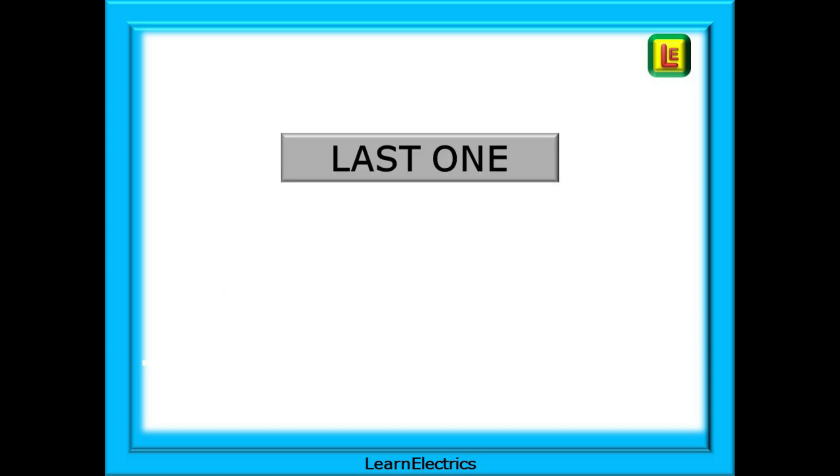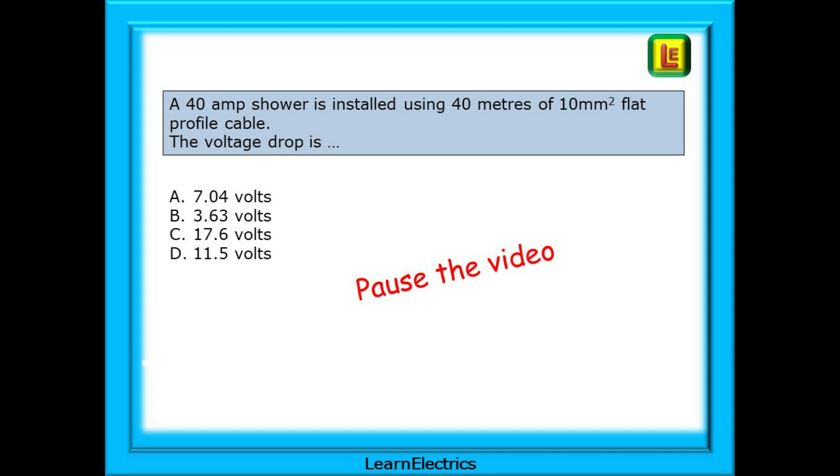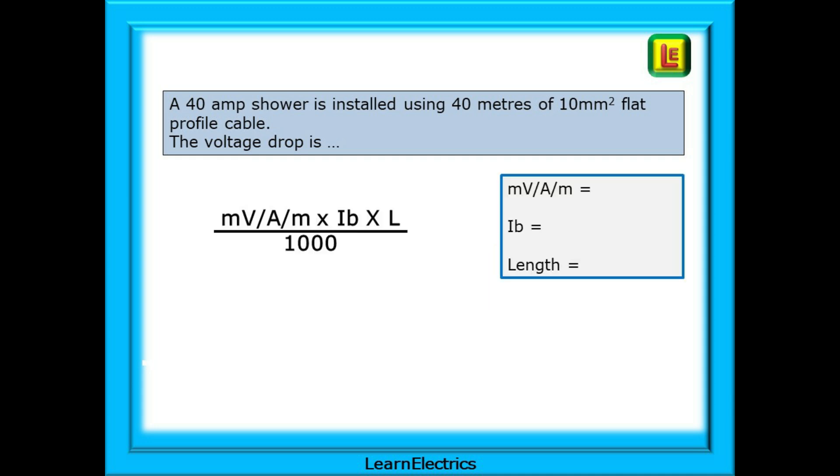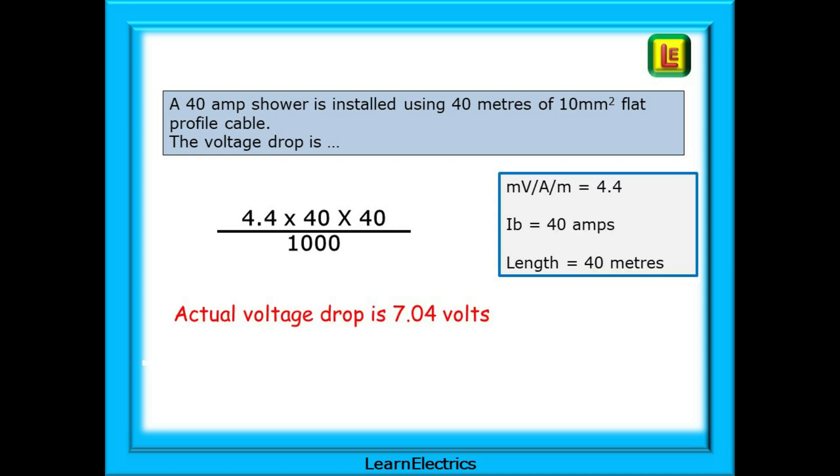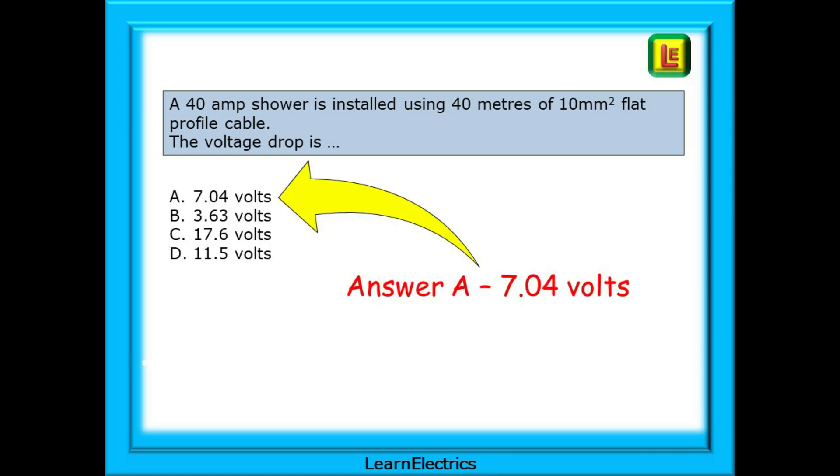And the last question for this video. A 40 amp shower is installed using 40 metres of 10 square millimetre flat profile cable. The voltage drop is 4 potential answers. Choose the correct one. Again pause the video and work through the question yourself. Here's the formula. Complete the data in the blue box. Enter the data into the formula. Make your calculation and your answer should be 7.04 volts. Now choose an answer. Your answer choice should be A.